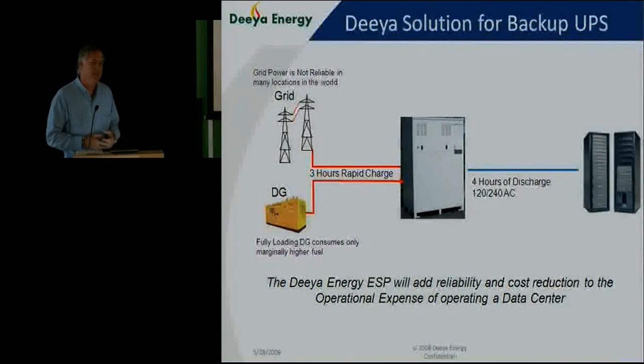But if you have sites where you're running your UPS quite a bit, and having to turn on diesel gensets to cover outages over a long-term scale, the Deeya system allows you to, first, reduce the money spent on energy storage since it's a one-time CapEx expense for a long period of time, and second, reduce the amount of diesel fuel you'd potentially need on site as an augmentation when you're losing power for a much longer period.